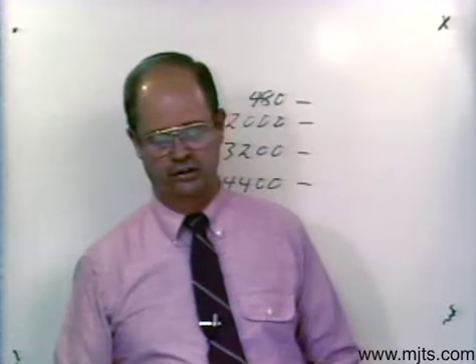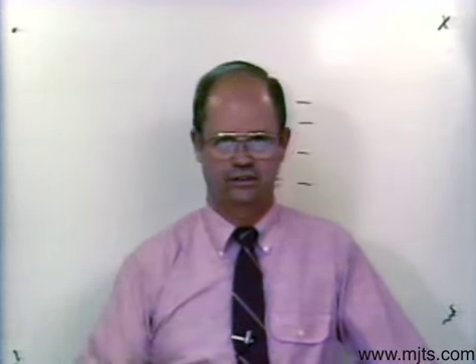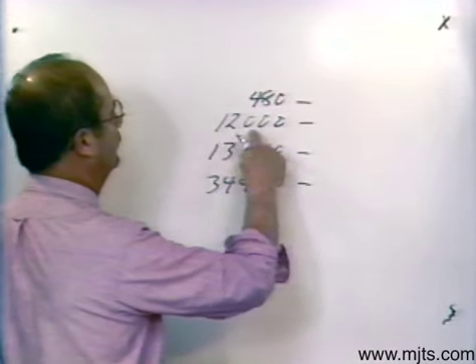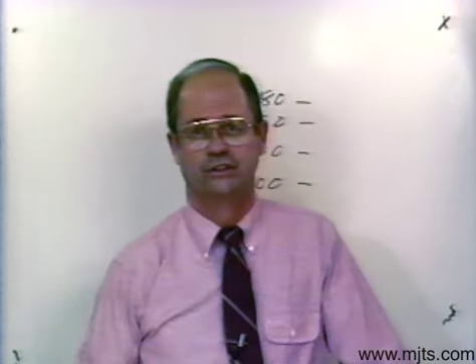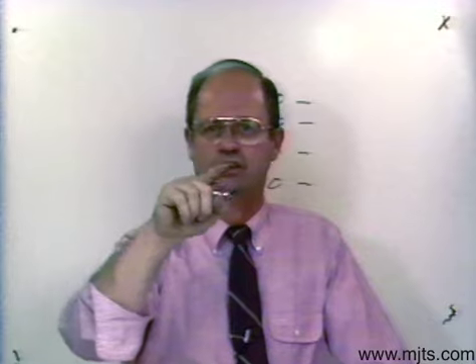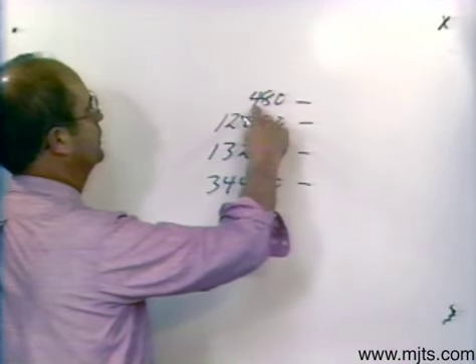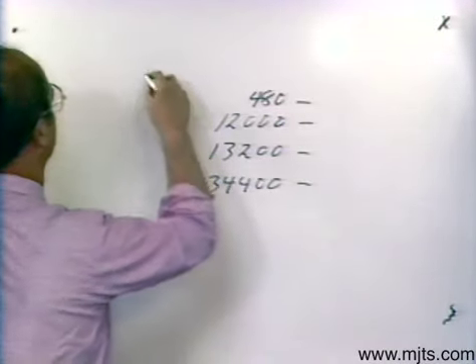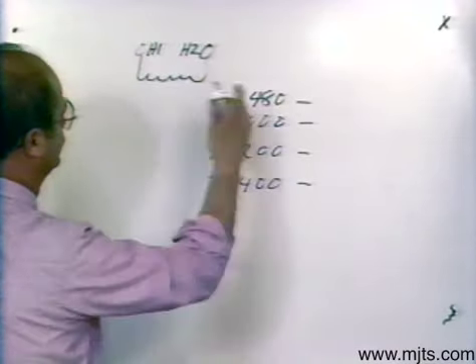When we say Y or delta, get used to thinking of it this way: a Y connection is phase to ground, and a delta connection is phase to phase. With these delta-only transformers, I would be connecting delta on a 12,000 volt system, or on a 480 volt system for dry type transformers installed inside a building for the consumer. If I draw those out, I would have two bushings — H1 and H2 — good for a delta connection only.